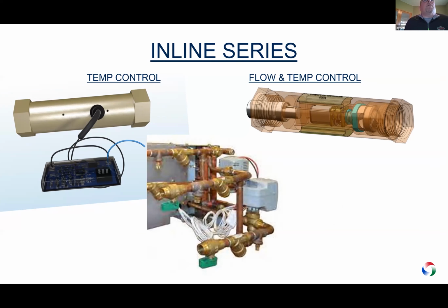With this new valve, we can either go temperature control or we can do flow and temperature control. But what's neat about this, it looks like a piece of pipe. There's no actuator that sits on top of this valve. The actuator is internal. The water flow actually goes around the actuator. So that means this thing can be mounted in any position. The little control panel that you see in the left-hand image can be mounted 20 feet away if you want, or you can mount it right on the pipe. So it's really kind of unique.